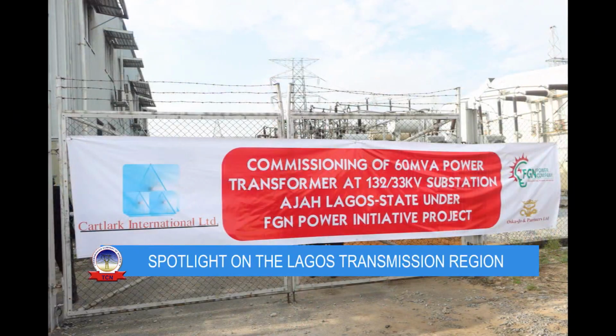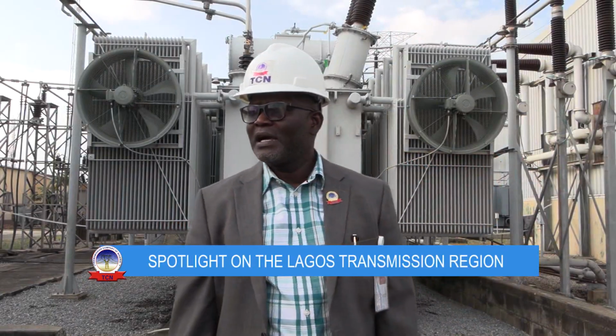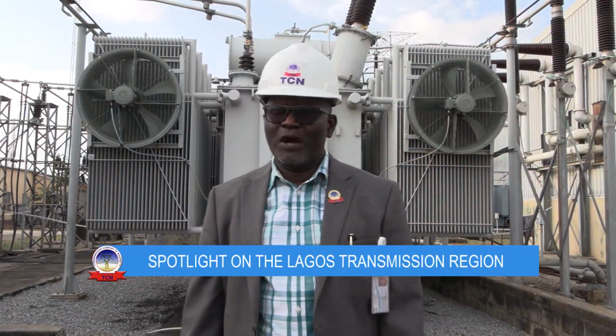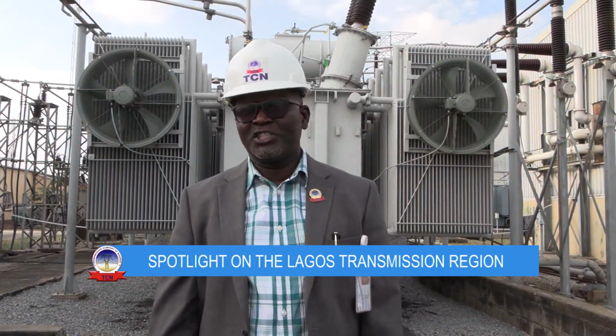The commissioning of the 60 MVA power transformer has increased the capacity of the substation from the 336 MVA. We just commissioned a new transformer sponsored by FG Power, which is part of the federal government initiative to improve power supply to Nigeria.